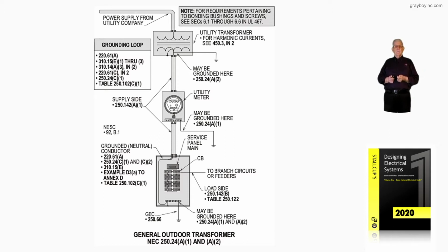ahead of your conductors. Now notice, if you wanted to review our UL standard 467, then we would review section 6-1 through 6-6, and we have parallel requirements there where you can find more about the pros and cons of grounding the transformer and the service equipment. Now next, let's look at the grounding loop.